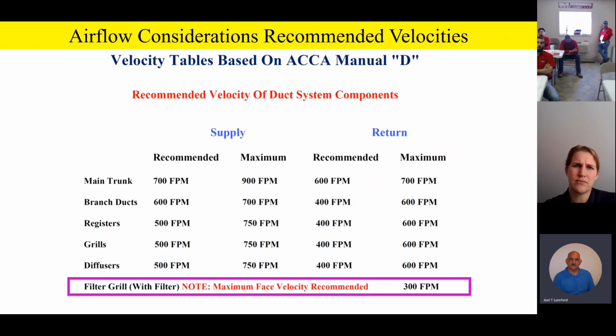Because remember, the outdoor unit is looking at all these pressures and temperatures on the refrigeration cycle, as well as outdoor temperature, and making intelligent decisions on where it needs to modulate or what capacity point it needs to be at. So, as a summary, if you have reduced airflow, the indoor coil is going to be colder than it normally would be under the same conditions of proper airflow. And the outdoor unit will interpret that as a reduction in capacity. So you might need 100% capacity, but it sees there's lousy airflow inside, so maybe it's only modulating at 85% capacity. You get the idea. So airflow becomes very, very critical and important whenever we do our airflow and duct design on a modulating system.